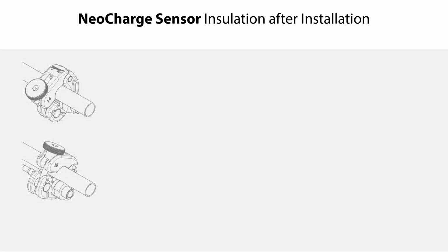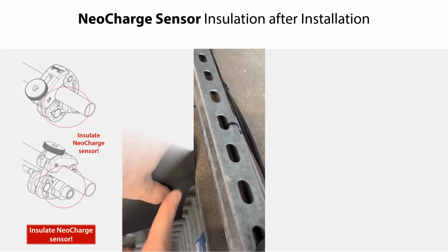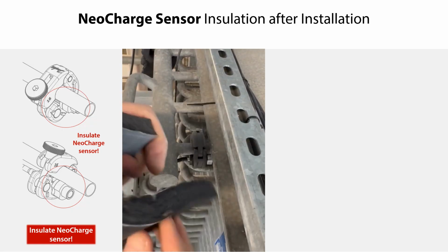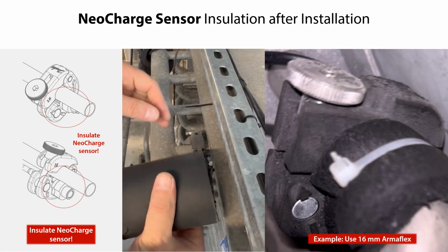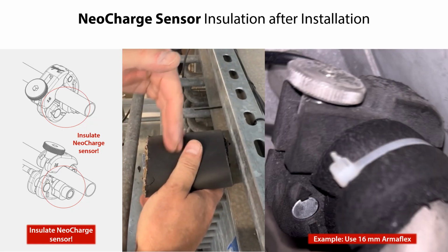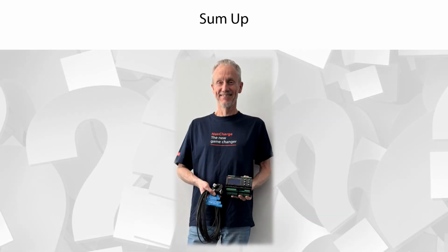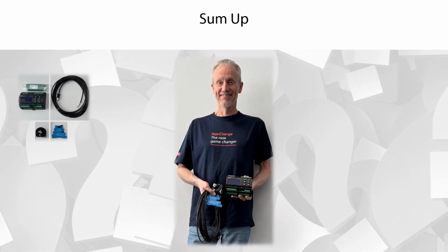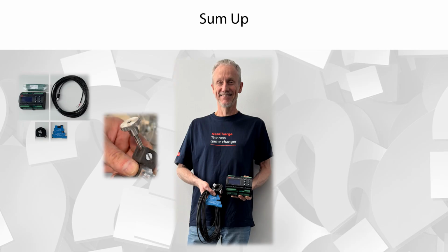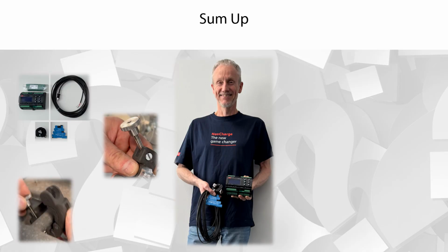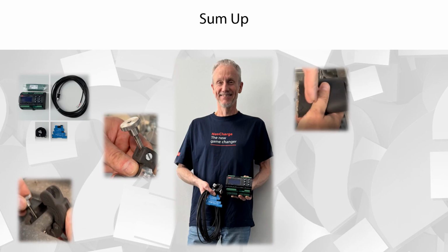Once the clamp and sensor mounting is completed, ensure to insulate the Neocharge sensor, as shown here. You can, for example, use 16 mm Armaflex as insulation. Okay, you now know what is included in the Neocharge box when unpacking it. And you know how to mount the Neocharge sensor in the Neocharge clamp and how to mount the sensor and clamp assembly correctly on the evaporator tube. Finally, you know how to insulate the Neocharge sensor after installation. All this ensuring a safe and energy efficient system operation.